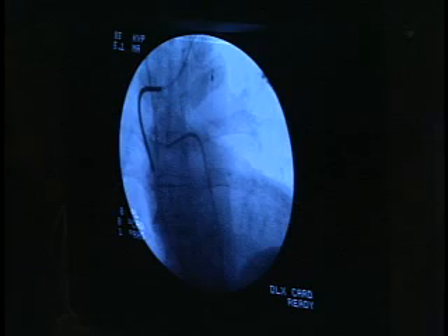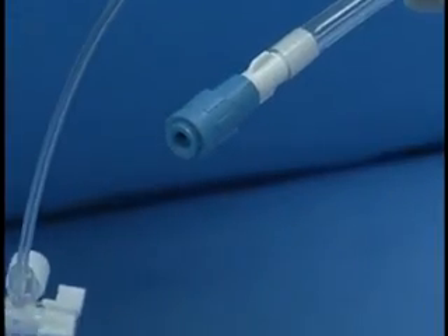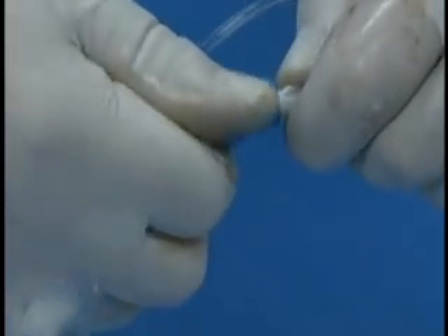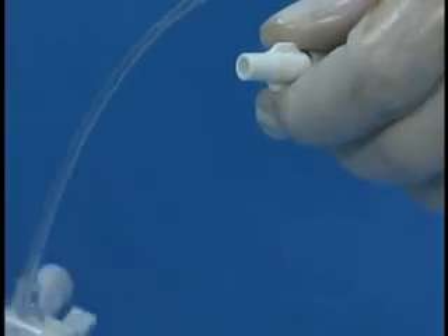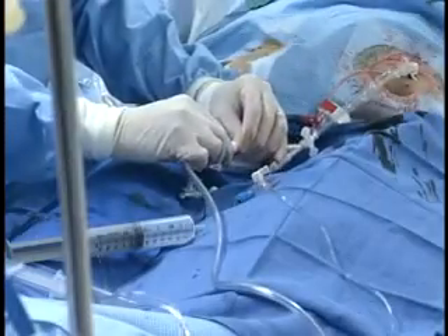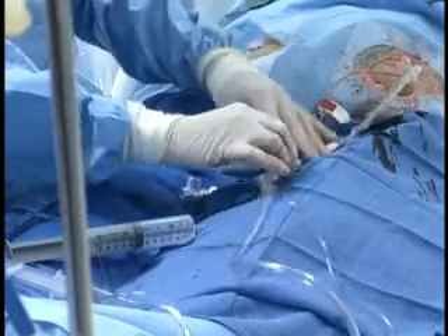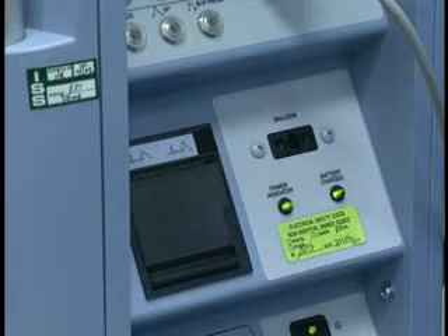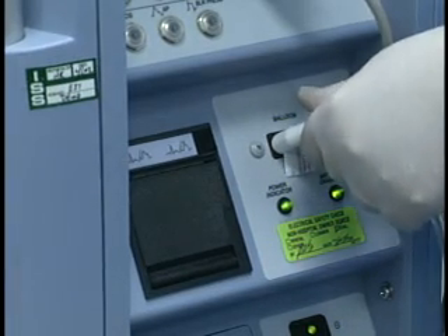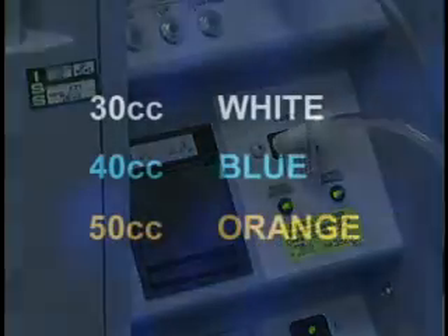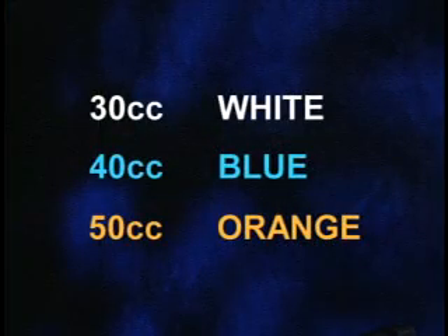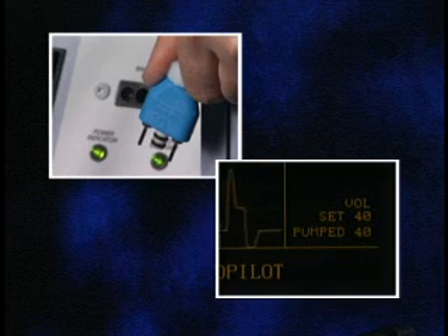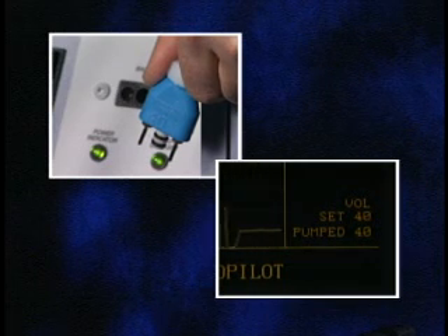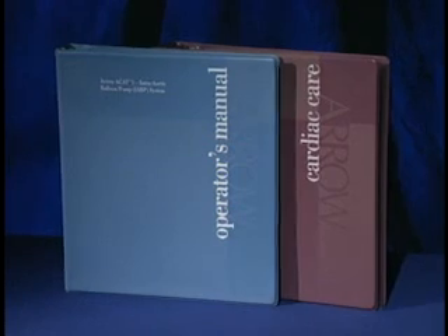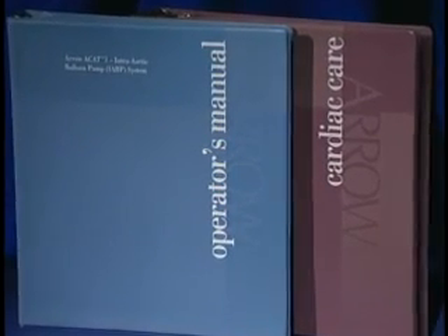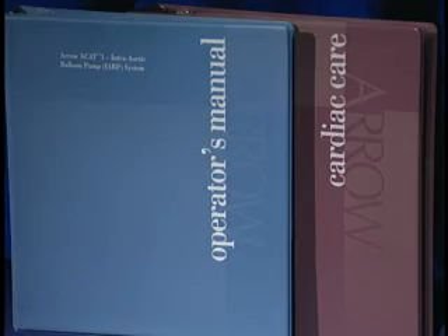Ensure correct IAB position. Release vacuum by removing the one-way valve with a gentle rotating motion from the connector on the short Tygon tubing. Attach driveline tubing to the catheter. Prepare for pumping by inserting the color-coded connector into the intraaortic balloon pump console. Arrow balloon connectors automatically determine the correct balloon displacement volume to be delivered by the pump. Follow the intraaortic balloon pump operating instructions for console startup and safe operation.